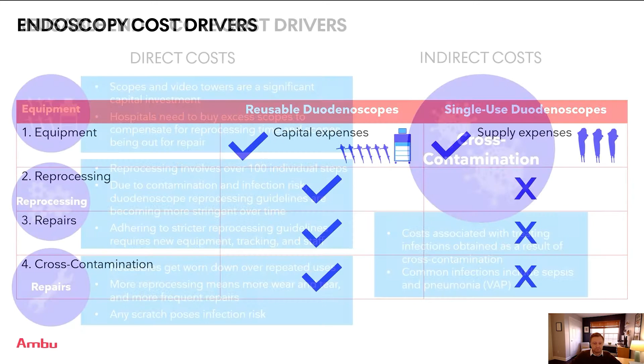So let's go a little deeper here on these cost drivers. On the equipment side, the scopes and video towers are a significant capital investment, and those costs are spread out over a number of years as that capital investment plays out and as the scope is used over its life cycle. And we often see that hospitals need to buy excess scopes to compensate for reprocessing time and for their scopes being out for repair. These duodenoscopes are very complex with the working channel and the elevator. There are many components that can break down and need repairs, and so that means that hospitals often have to have an extra duodenoscope available for those times when repairs are necessary if they're not given a loaner. So equipment costs are very considerable.